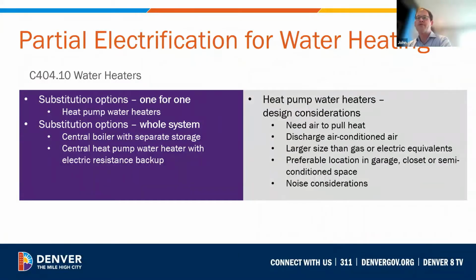Heat pump water heaters are a good substitute for gas storage and electric storage water heaters. For larger apartment buildings, central heat pump water heaters are available that have an electric resistance heater for backup. There are a few important design considerations for heat pump water heaters. Their operating conditions are typically limited to 40 degrees Fahrenheit and higher, so they're best located in semi-conditioned spaces such as garages, closets, or basements. They require either sufficient clearance or ventilation or venting. If located in a conditioned space, they will tend to draw some heat from the surroundings, leading to an increase in heating requirements. They should also be located in a space with some acoustic separation from the occupied space, given their general acoustic performance.